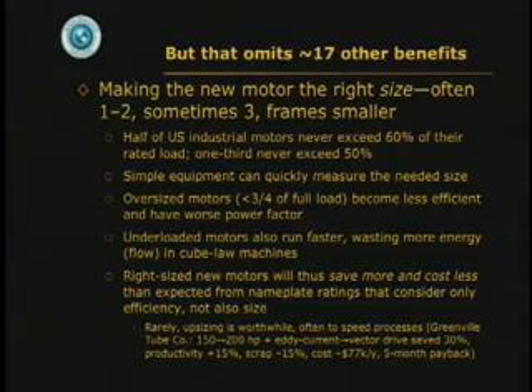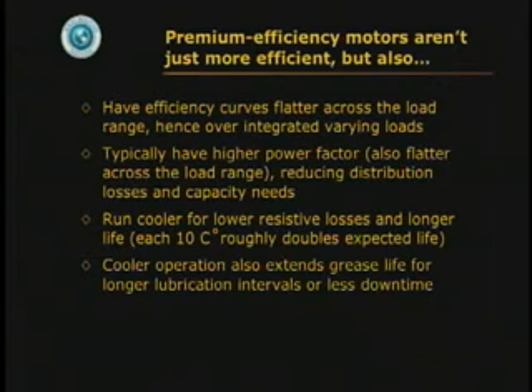Occasionally upsizing is worthwhile, not very often. Premium efficiency motors are not just more efficient. Their efficiency is flatter over a range of load. They have a higher power factor, also flatter across the range of load. They run cooler. This greatly increases their life and it extends the grease life of the lubricant. And also they come with more durable bearings, which avoids most motor failures.